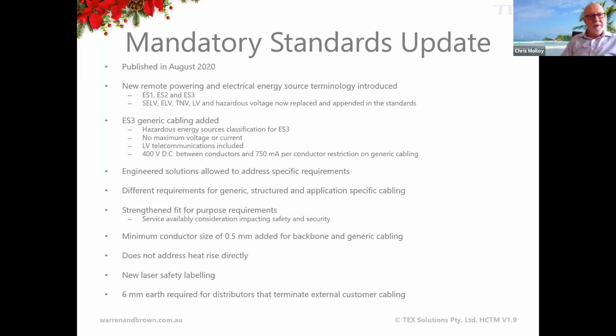According to the standard, there's no voltage or current limiting on ES3, so it is truly a hazardous service. We used to define current limited or voltage limited for the outgoing terminologies, so just be mindful that ES3 is a hazardous service. If you're putting in ES3 services with no voltage and current limiting, you want to make sure your equipment is compliant from a regulatory standpoint. We're talking about 400 volt DC between conductors and a 750 milliamp per conductor restriction on generic cabling. So you can deliver hazardous services down generic cabling, is what it means.